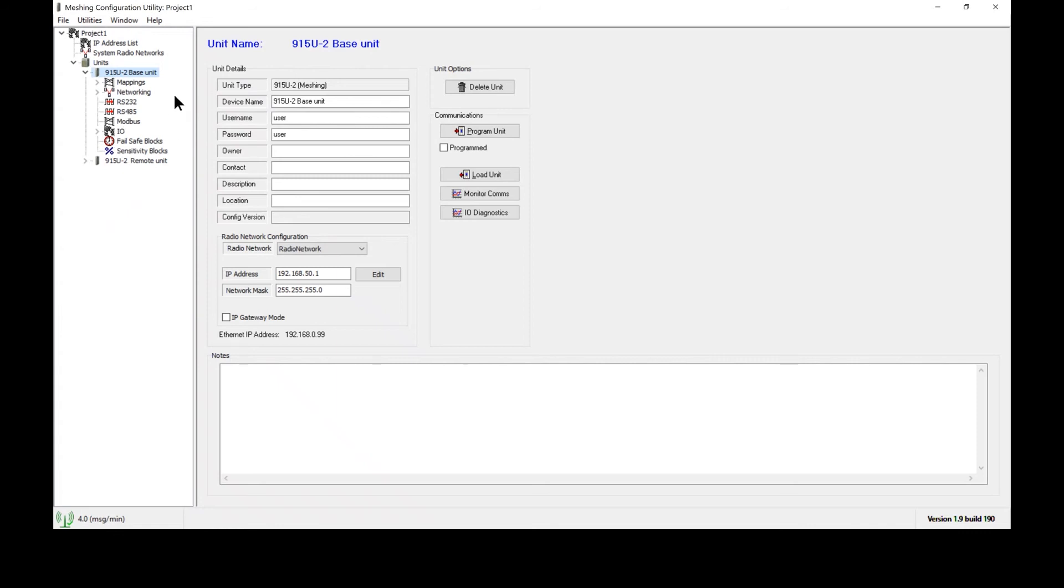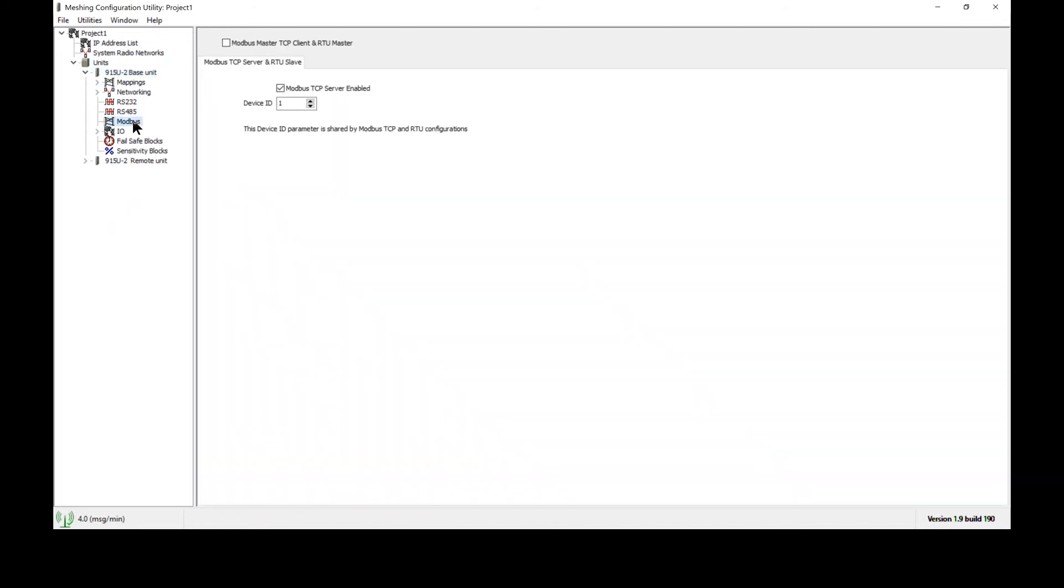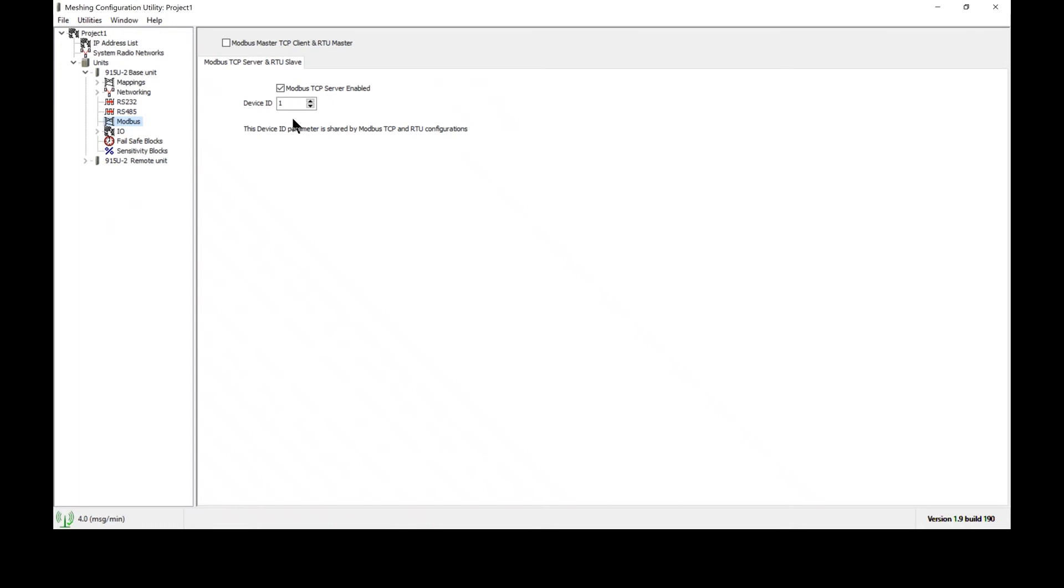To set up Modbus communications I'm going to go ahead and click on Modbus. If I am just setting up this radio to act as the Modbus server, then this is the only box that I need to make sure these two parameters are enabled and we have a device ID. That's the only piece of information that needs to be done and this radio will now respond to all Modbus TCP client queries that are directed to it.